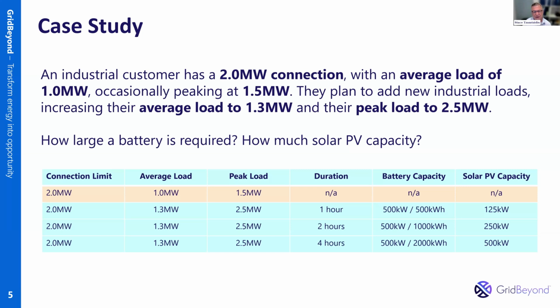So if we had a peak of 2.5, the battery will be determined by how long you need that, how long the battery needs to operate. In the example that James offered, he had a small spike, which meant not much energy, which meant not many megawatt hours. But if you've got a 1 hour duration spike, you'll need to match it, which is a 500 kilowatt battery, in this instance 2 hours. So it's proportional to how long that spike is there. The 500 kilowatts is the amount of power above the connection limit. In this case, it's 500 kilowatts.